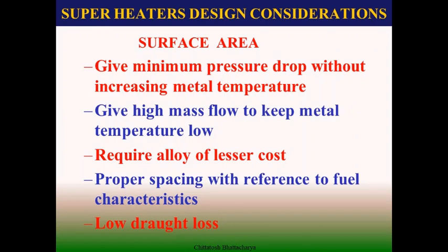In general, there is an average 30 to 35 degree temperature difference between the tube metal and the superheated steam along the flow passage. As you see, in the LTSH portion we have a cross flow arrangement, but in the primary platen and secondary superheater the flow pattern of the flue gas and steam is parallel flow.